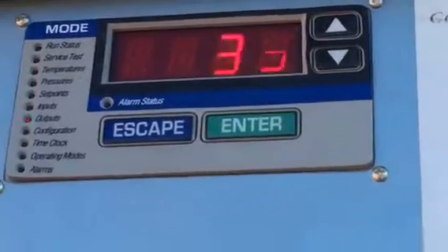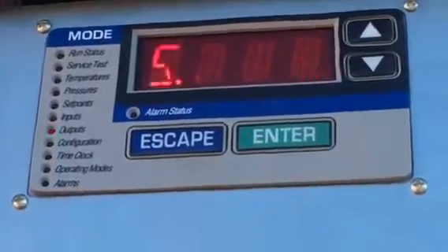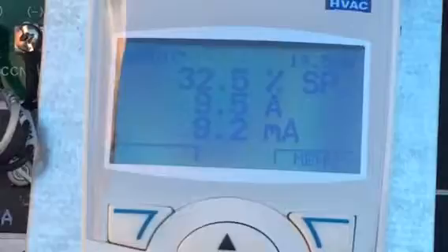And then, my next step is the S.VFD would be what? Speed for the VFD, and it shows me 33%, 32.5%. So they're almost equal. Another item you'll see on your ABB keypad, next to where it says auto, and always make sure that says auto, is the spinning arrowhead, clockwise or counterclockwise.